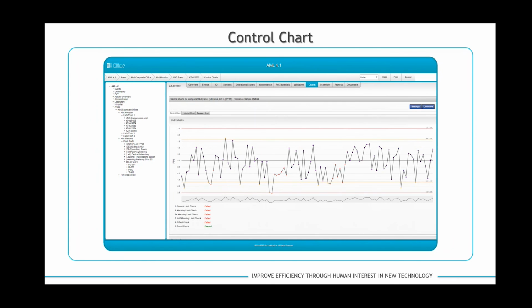Your instrument might have validations that are perfectly within its limits, but it might be trending. That's something you can see through control charts, for example, or it might be slightly off center mark, just above it. Then you want to do a calibration to bring it back to the center mark.